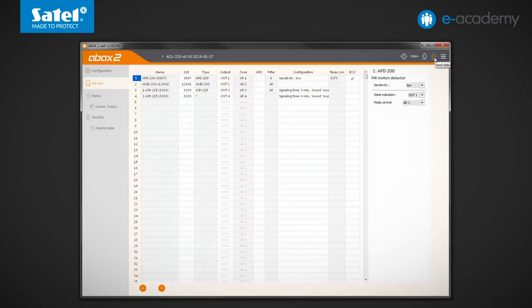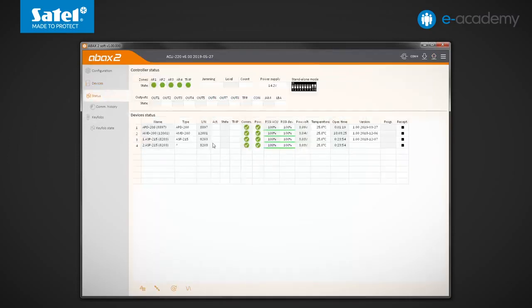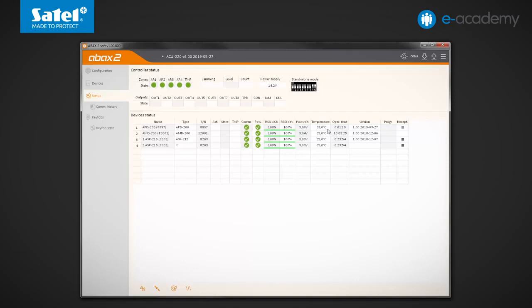Return to the Status tab and wait for the data from the detector to be received. Okay, the displayed value is higher than the previous one by 3 degrees, though the temperature around the motion detector has not changed. So you can see that the correction has been taken into account.